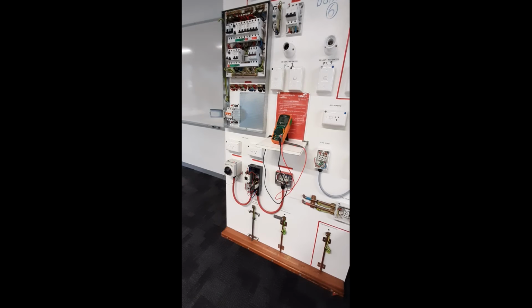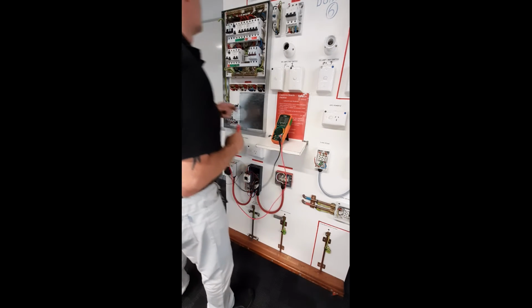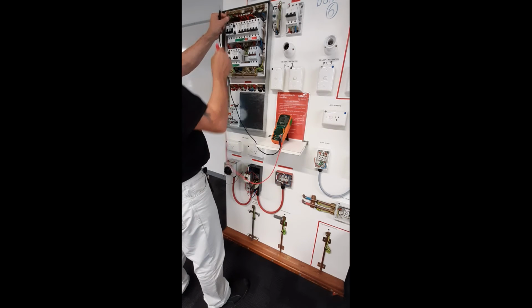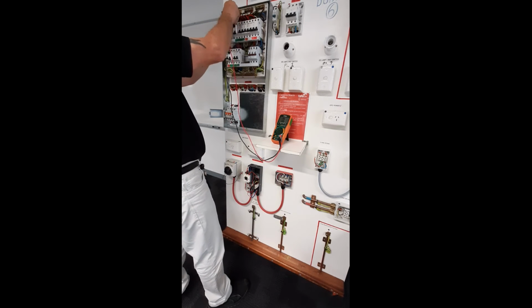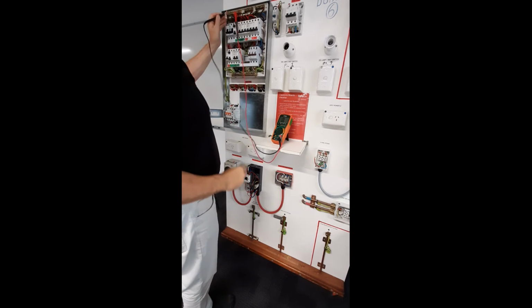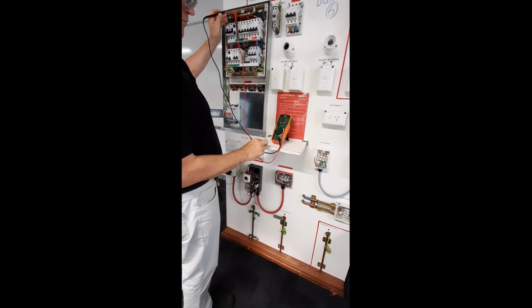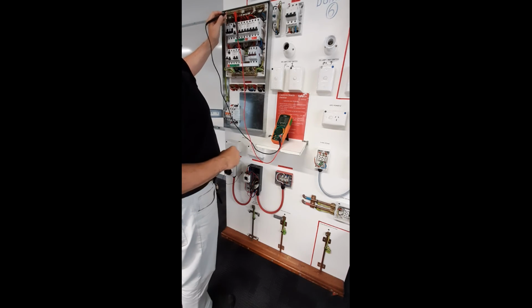Neutral conductors. Disconnect each circuit neutral from the neutral bar in the switchboard in turn. Test between the disconnected neutral and the neutral bar. Disconnected the first neutral. Open line, I have infinity.